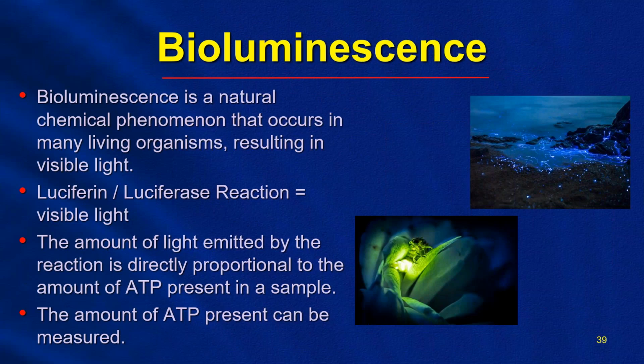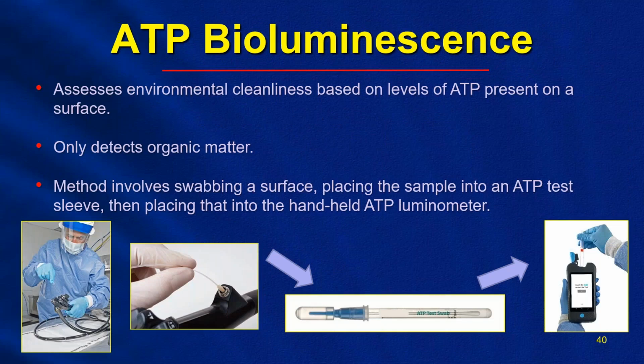The presence of ATP on medical devices, instruments, or surfaces may be an indicator of residual contamination. Modern bioluminescence tests are based on the reaction of luciferase extracted from fireflies. The substrate is known as luciferin, and the reaction is known as a luciferase reaction, based on the enzyme. The amount of light emitted is called a relative light unit, measured in RLUs, and it is directly proportional to the amount of ATP present in the sample. So the higher the amount of ATP, the larger the light burst. The ATP luminescence test is based on the measurement of ATP present on a surface.